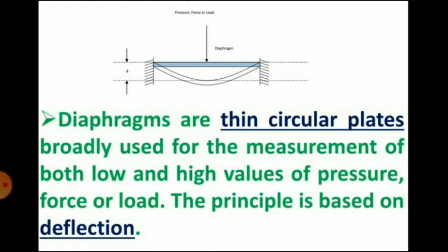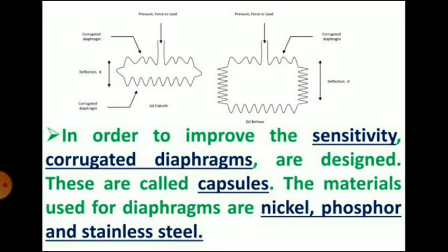A specially designed strain gauge is often used, consisting of four strain gauges, with two measuring the strain in a circumferential direction while the two measure strain in a radial direction. The four strain gauges are then connected to form the arms of the Wheatstone bridge. In order to improve the sensitivity, corrugated diaphragms are designed. You can see the corrugated diaphragms in the diagram. These are called capsules. The materials used for diaphragms are nickel, phosphor bronze and stainless steel.